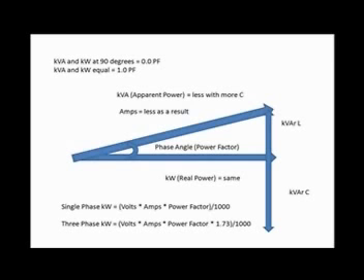You have not changed, however, your kilowatts or real power, what you're actually billed on. And this is where the scam comes in. They demonstrate it in current only. If you want real proof, have them show you a change in power factor or kilowatts.